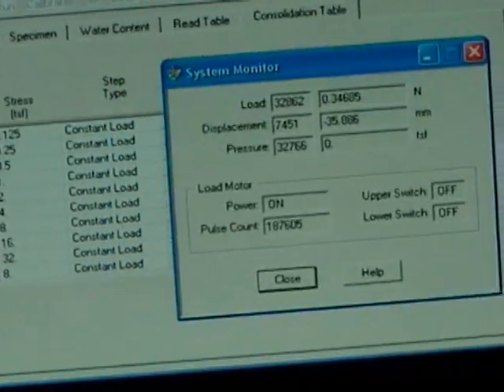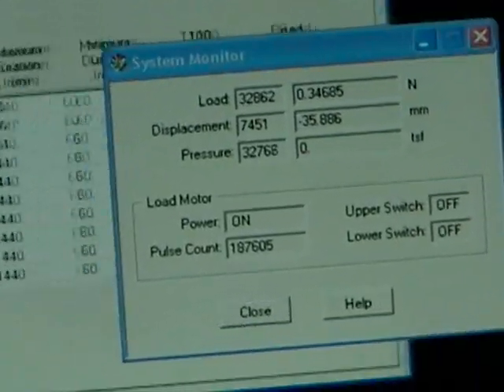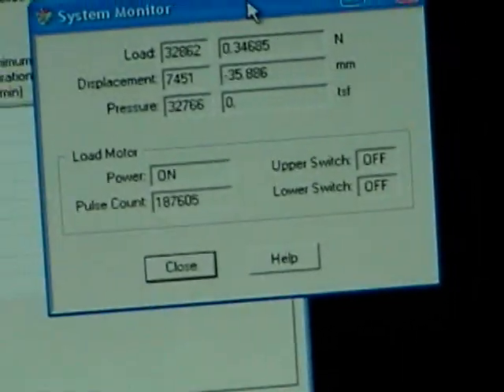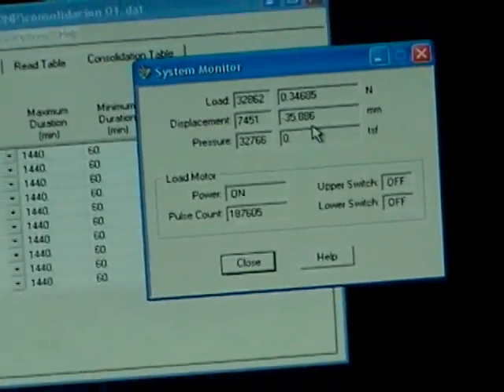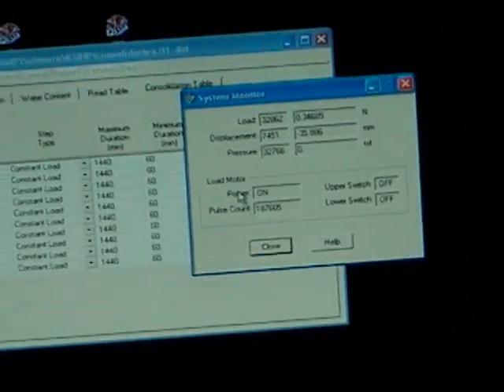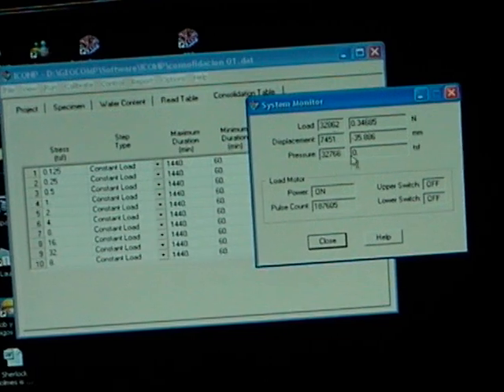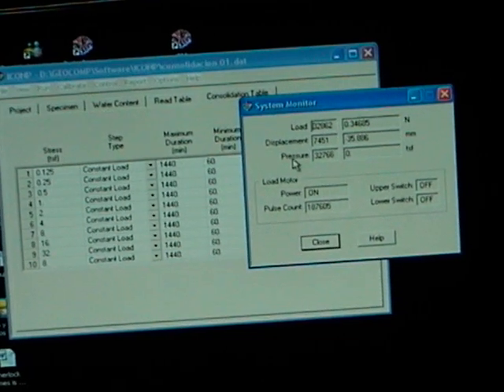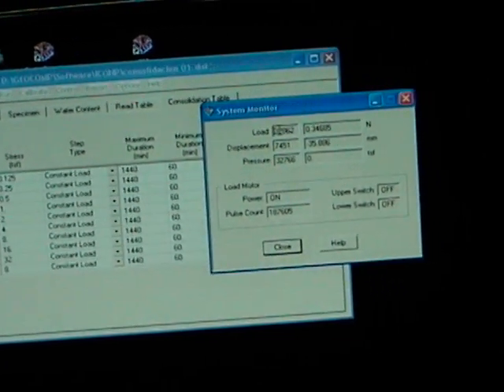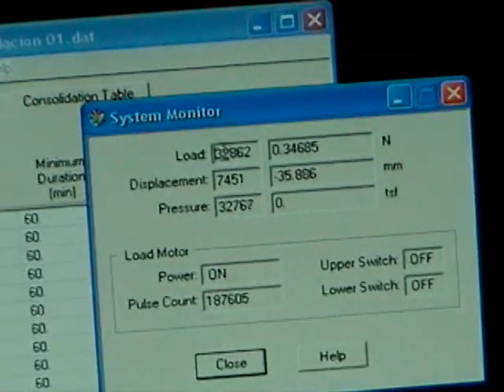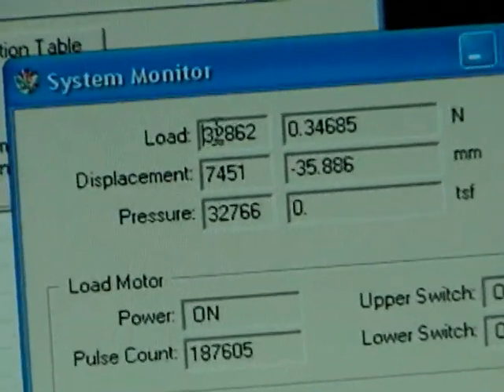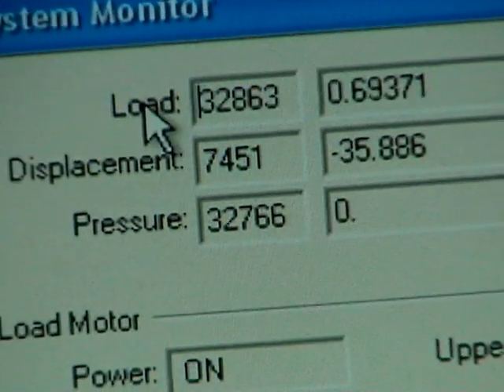You want to make sure that you are communicating with the LoadTrac II, with the system. The power should be on. The values of the sensors should be about 32,000. Maximum is 65,000 or zero.